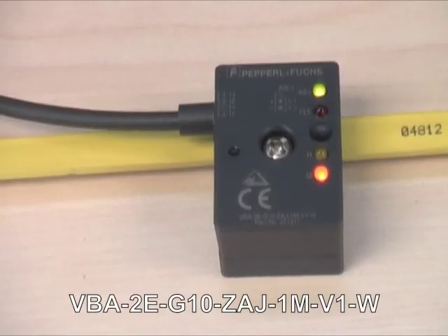For 2011, Pepperl & Fuchs is introducing three distinct G10 models. This version offers two inputs on one pigtail. Use it when the installation requires exactly one sensor of any kind, 2-wire, 3-wire or 4-wire at a location. When using a 4-wire sensor, both sensor outputs are connected.